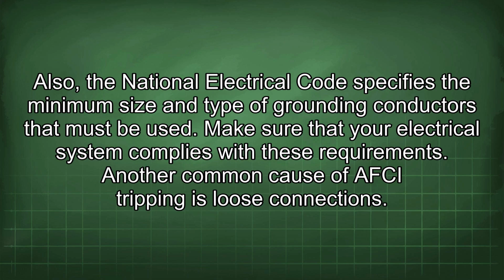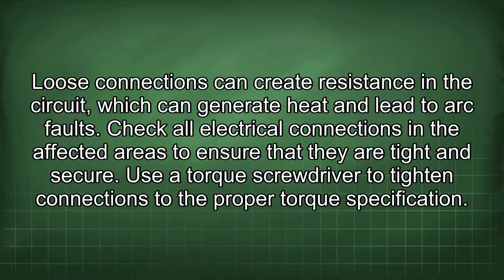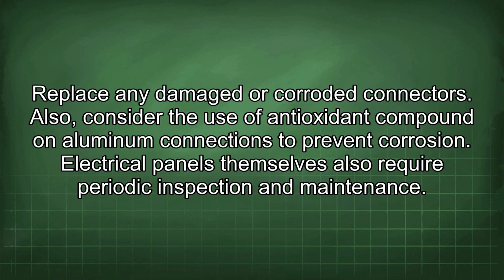Another common cause of AFCI tripping is loose connections. Loose connections can create resistance in the circuit, which can generate heat and lead to arc faults. Check all electrical connections in the affected areas to ensure that they are tight and secure. Use a torque screwdriver to tighten connections to the proper torque specification. Replace any damaged or corroded connectors. Also, consider the use of antioxidant compound on aluminum connections to prevent corrosion.